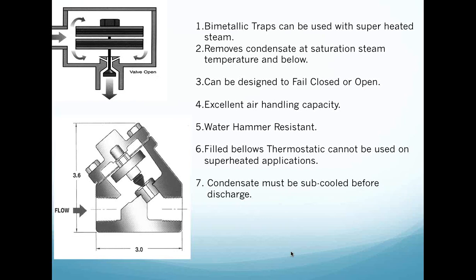So it is possible with a thermostatic technology that you will have a small portion of your piping just prior to the steam trap. There will be a leg of subcooled condensate that will lay in there, and I have had nipple threads eaten out within 3 years because of this particular type of trap technology inside of a system. Now, the trap function, the system worked fantastic, but because of the actual ability to subcool, follow the saturation curve just underneath it, we subcooled that liquid, and we ended up having that degradation build up in that 8 to 12 inch section or zone just prior to the trap.